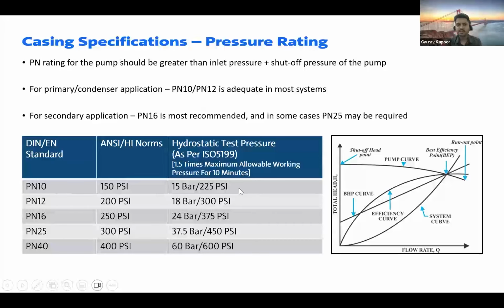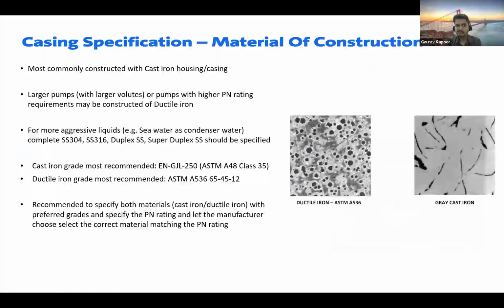As per our experience, we have seen primary and condenser applications to be PN10, whereas for secondary applications, PN16 is mostly recommended. Now for the material of construction for the casing, cast iron is more than sufficient for smaller size pumps, but for pumps with large volute size or higher PN ratings, ductile iron is more suited. Whereas for aggressive liquids, for example when we are using seawater as condenser water, super duplex or duplex stainless steel is always recommended.